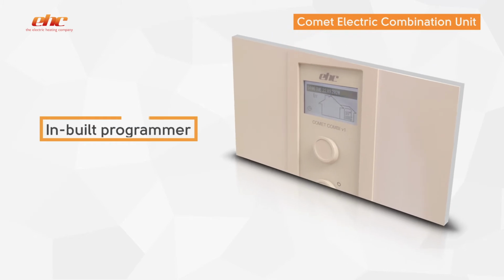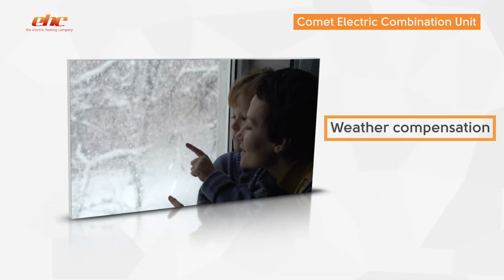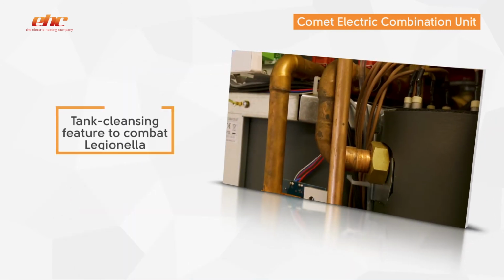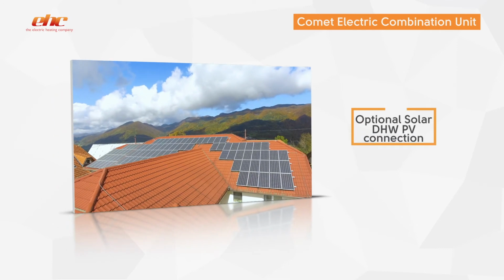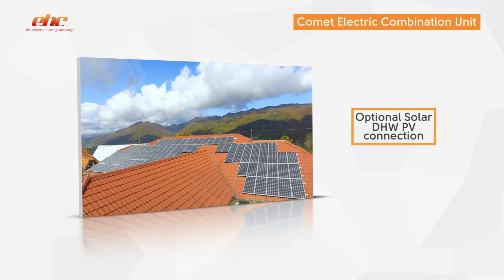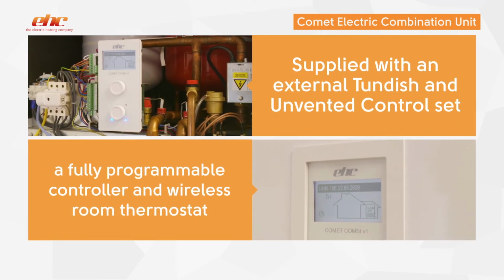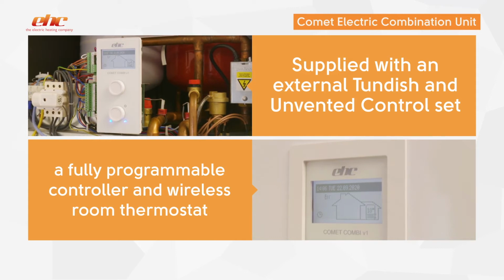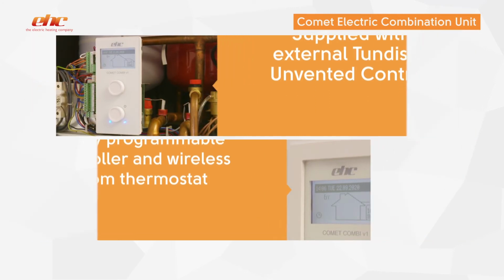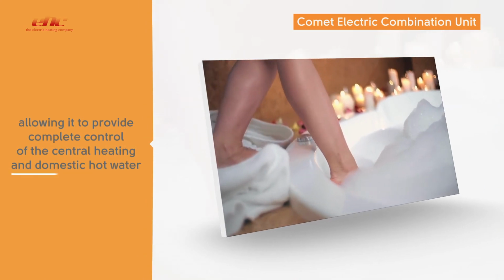Among its design features, the unit has an inbuilt programmer, weather compensation, a tank cleansing feature to combat Legionella, as well as an optional solar DHW PV connection. The unit is also supplied with an external tundish and unvented control set, a fully programmable controller and wireless room thermostat, allowing it to provide complete control of the central heating and domestic hot water.